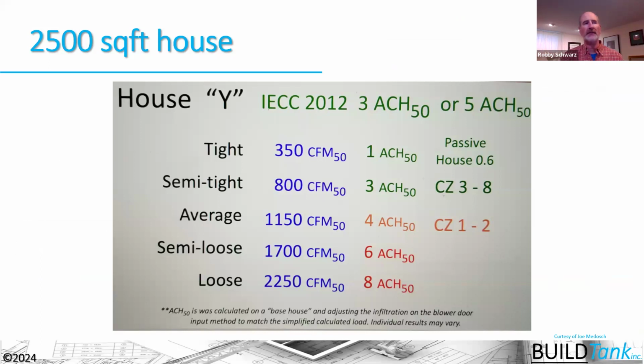So tight, I wanted to give you some kind of frame of reference from tight to loose here. We could see that a tight house is in the range of 1 air change per hour. A loose house is in the range of 8 changes per hour. So if you do see these rules of thumb, the default entries entered into the software, you never want to see anything less than semi-tight because the code requires at least 3 air changes per hour. And we know that the state average is at 2.5 air changes per hour.